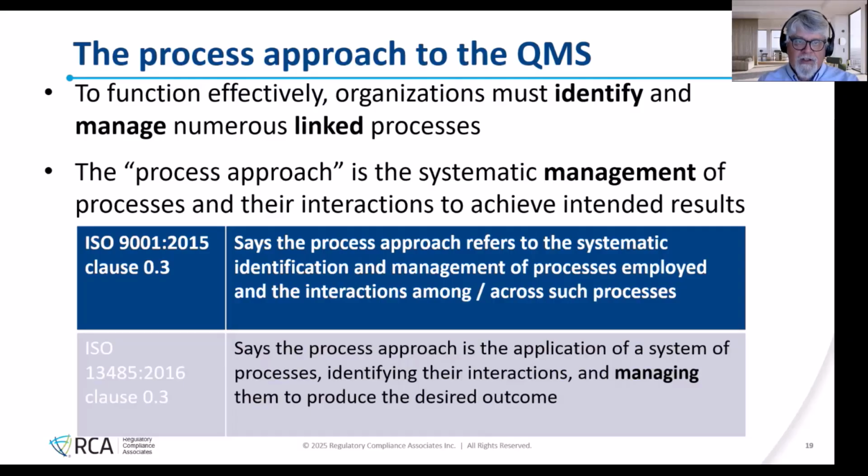So let's talk a little bit about the process approach to the quality management system. This is coming from the ISO standard, particularly 13485:2016 in clause 0.3. This became really evident when MDSAP came into being, MDSAP, Medical Device Single Audit Program, which we'll have slides on in a minute. There are 5 countries involved in that.